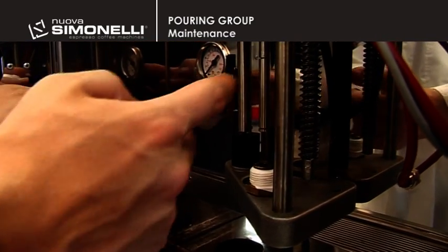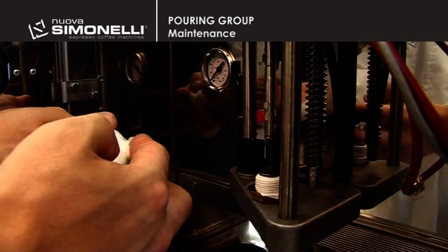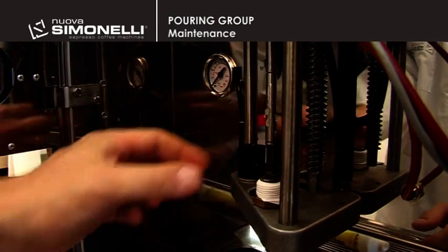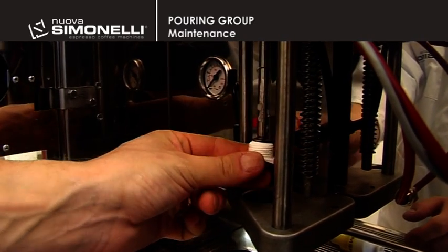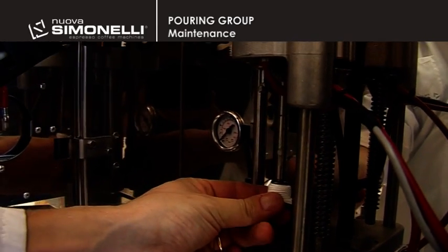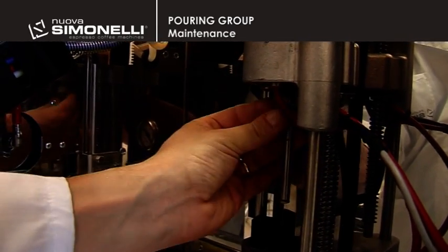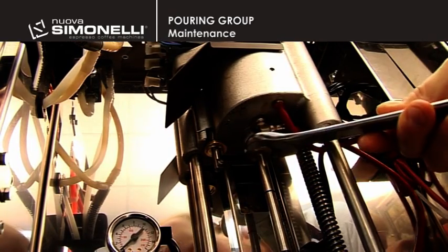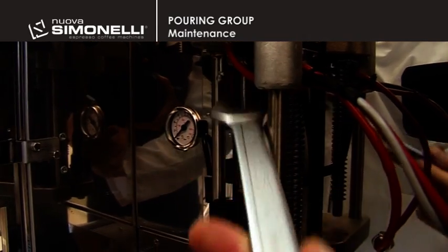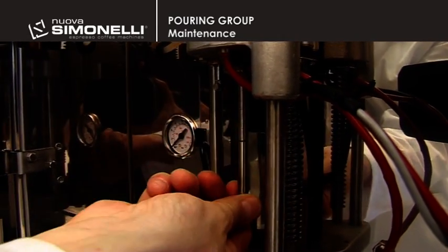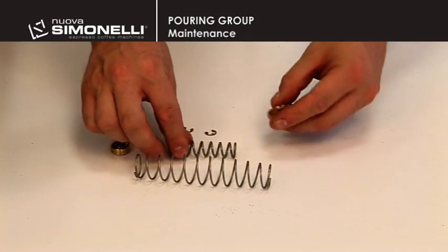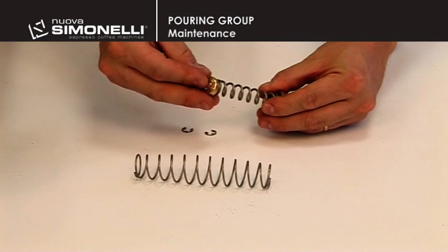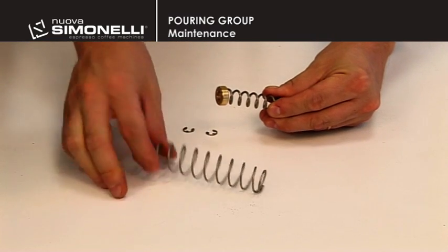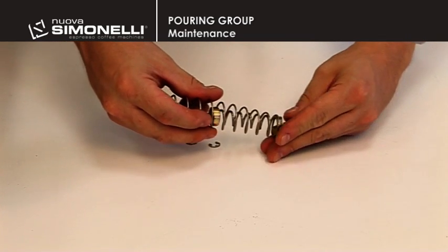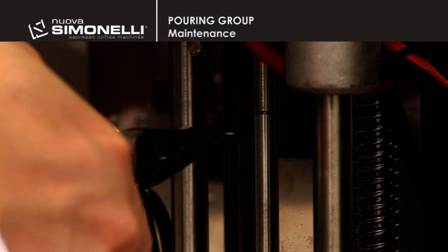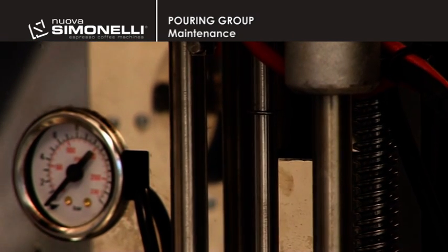Use food-grade lubricant to grease the bottom piston shaft and slip on the new seal and feet. Tighten the screw with a 21mm wrench and make sure that the bottom piston can complete its stroke freely. The engineer will then insert the supports and springs. Fit the O-ring in the middle of the bottom piston shaft together with the previously assembled springs.